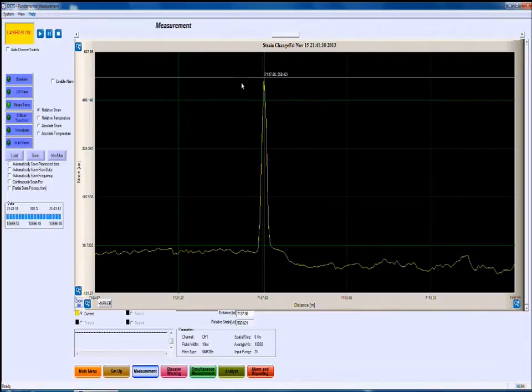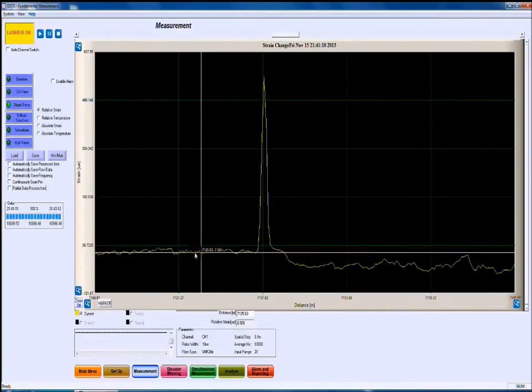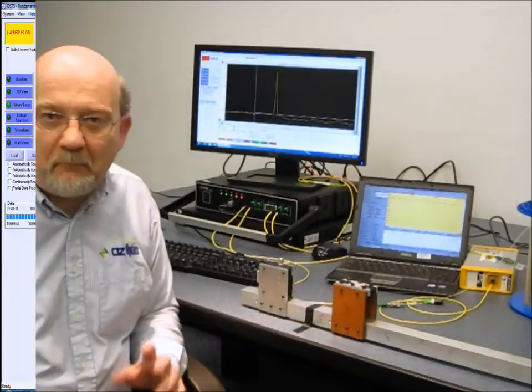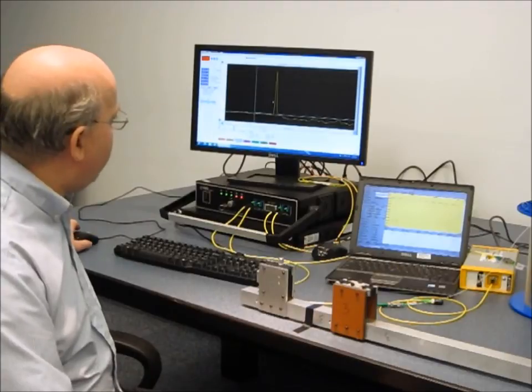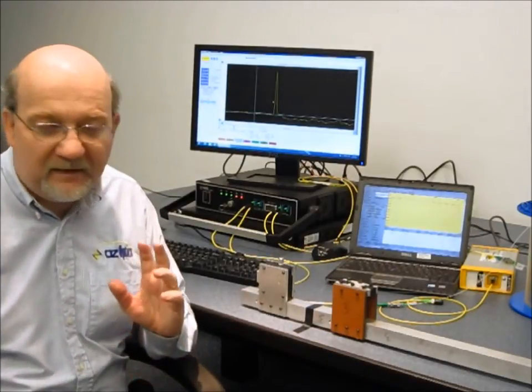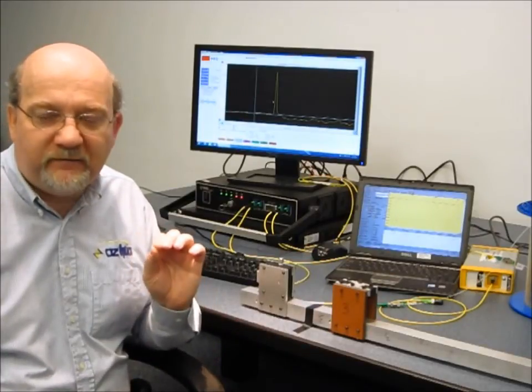The peak here corresponds to a strain of 558 microstrain. For comparison, our background signal is around about 7 microstrain. So our signal that we're seeing here is roughly 70 times stronger than our background signal. So we have a very good signal-to-noise ratio and can easily detect this strain, which was so hard to see using the OTDR system.